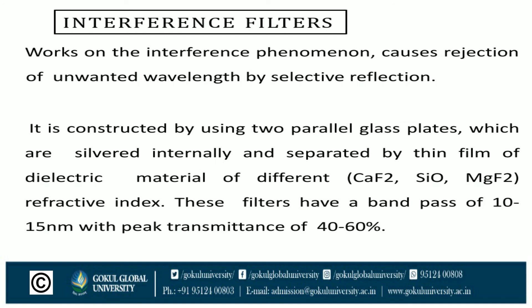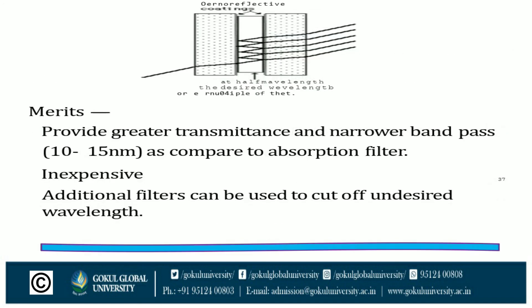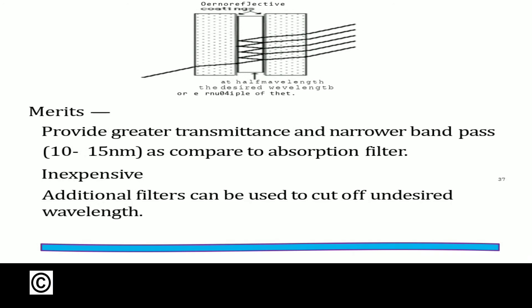These interference filters have a band pass of 10 to 15 nanometers with peak transmittance of 40 to 60 percent. The merits are greater transmittance and narrower band pass of 10 to 15 nanometers as compared to absorption filters. They are also inexpensive, and additional filters can be used to cut off undesired wavelengths.